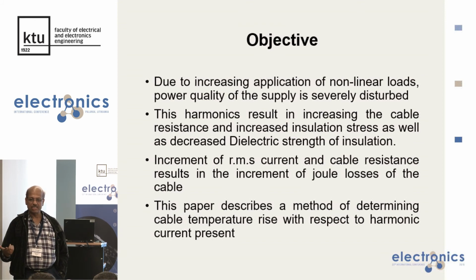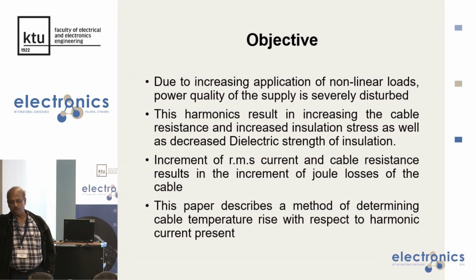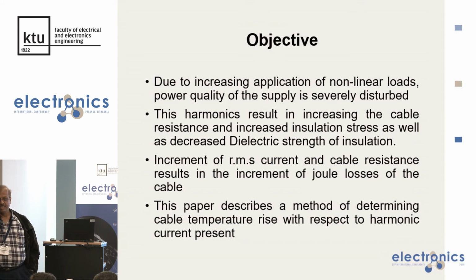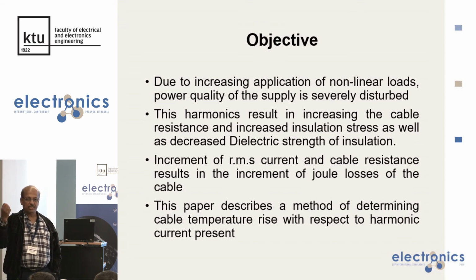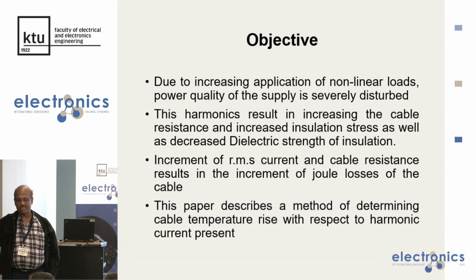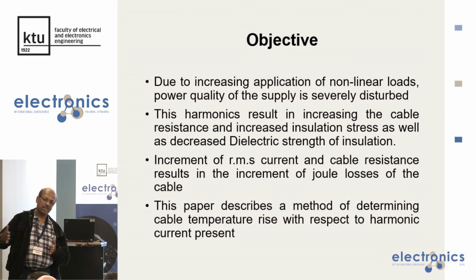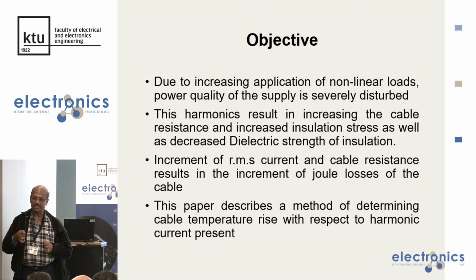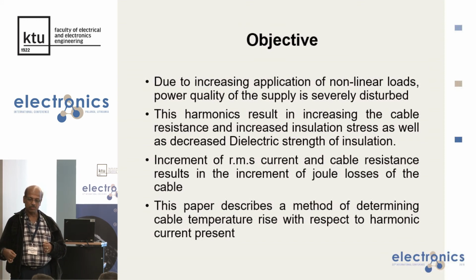What is this more resistance? It is basically the skin effect in a power system over a transmission line. We know that whenever frequencies are higher, skin effect is there, and skin effect gives more resistance in the conductor cables. So the I squared R heating, that means the heat generated in the conductors, will be more for the third harmonic component, the fifth harmonic component, and the seventh harmonic component.